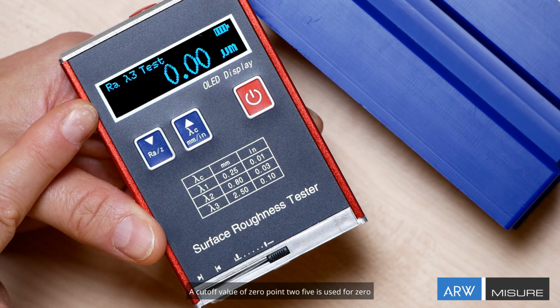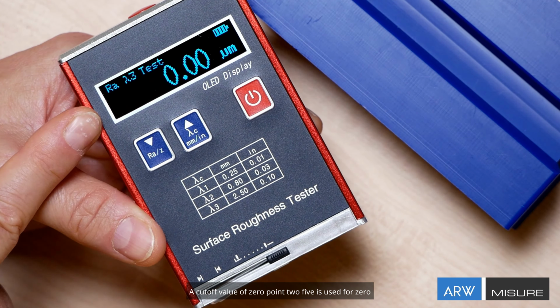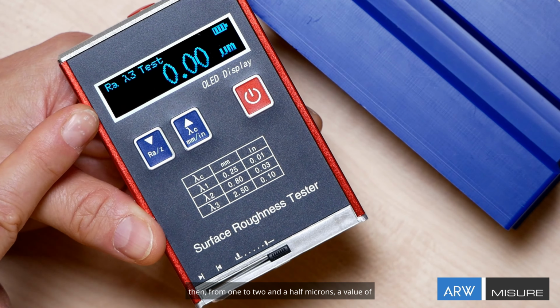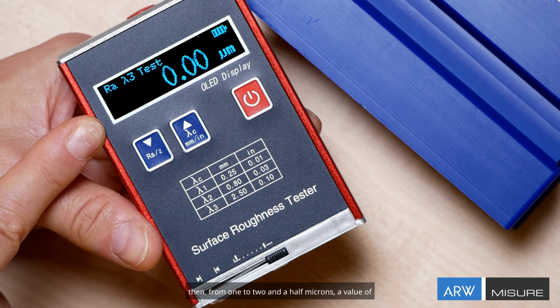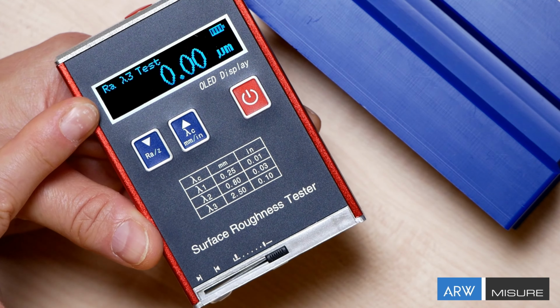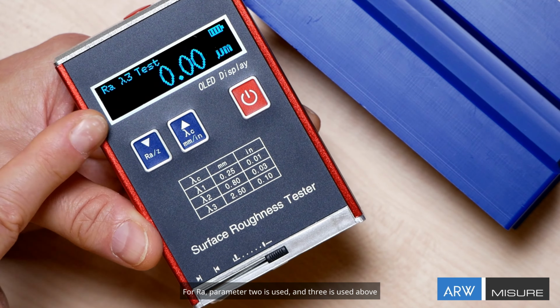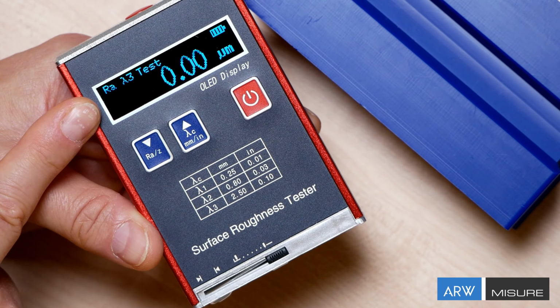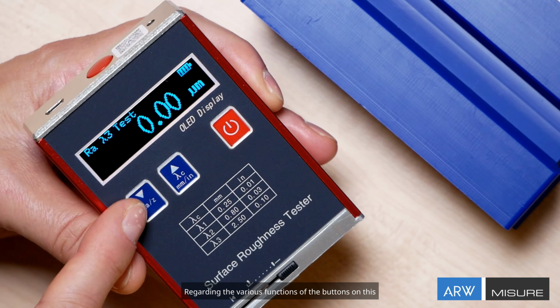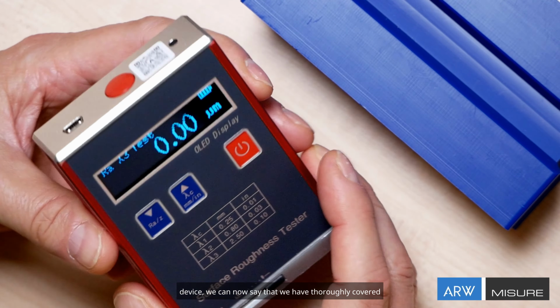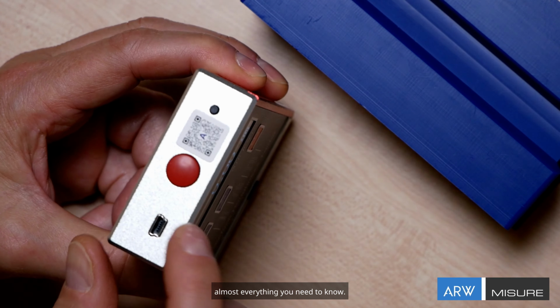A cutoff value of 0.25 is used for 0 to 1 micron of surface roughness in Ra, then from 1 to 2.5 microns, a value of 0.8 is used for Ra, parameter 2 is used, and 3 is used above 2.5. Regarding the various functions of the buttons on this device, we can now say that we have thoroughly covered almost everything you need to know.